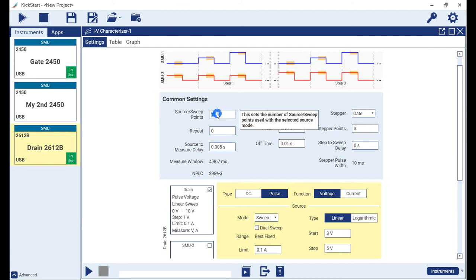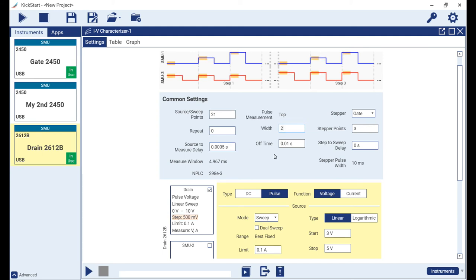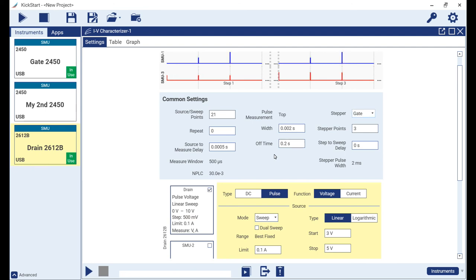Let's now modify some of our other common settings, changing the source sweep points to 21, the source to measure delay to 500 microseconds, the width to 2 milliseconds, and the off time to 200 milliseconds. Note above in the waveform viewer area that we get an approximate visualization of what is to be expected of each active SMU channel output.